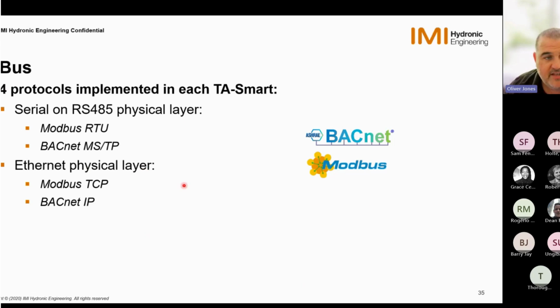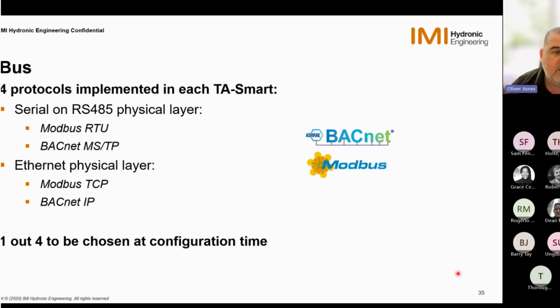And then we have our Ethernet physical layer, so we can wire our Ethernet cable into the Smart box and do Modbus TCP or BACnet IP, which is ridiculously fast. And one of the 4 is to be chosen at configuration time, when you're actually setting up and commissioning the valve itself.